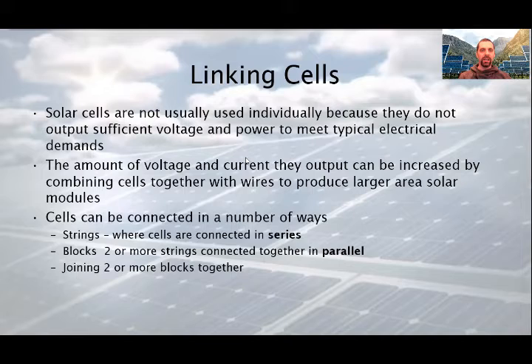Solar cells are not usually used individually because they do not output sufficient voltage and power to meet typical electrical demands. We know already that the common single junction silicon solar cell can produce a maximum open circuit voltage of approximately 0.6 to 0.7 volts. But that is not enough for anything. The amount of voltage and current output can be increased by combining the cells together with wires to produce larger area solar modules. Cells can be connected in a number of ways, strings for example, where cells are connected in series, then blocks, where two or more strings connected together in parallel, and finally joining two or more blocks together.